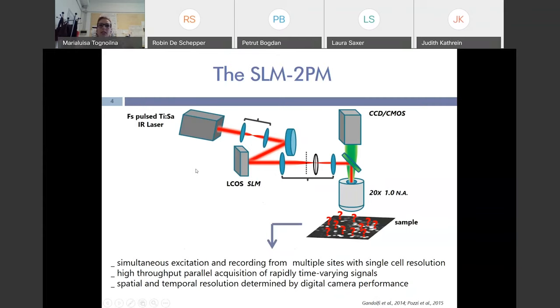To study the granular layer activity, we developed in our lab a particular kind of two-photon microscope: the spatial light modulator two-photon microscope. This uses the spatial light modulator device to split the laser beam coming from a two-photon pulsed laser. The SLM splits the incoming laser beam into multiple beamlets that are directed onto the sample, where they elicit fluorescence that is collected by a CCD or CMOS camera. In this way, we are able to simultaneously excite and record from multiple sites while maintaining single-cell resolution.